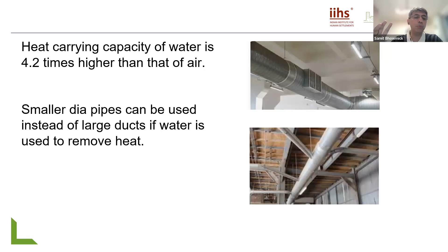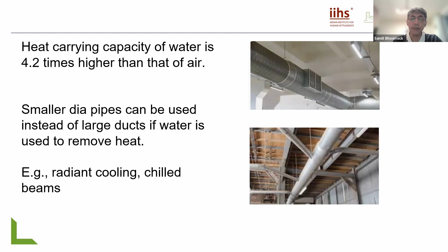It's been used in a lot of new buildings, at least in dry and convenient areas, with systems like radiant cooling or chilled beams, where the chilled water is brought as close as possible to the cooling load. This way you use smaller pipes to remove heat rather than large ducts, which would conventionally be used. Not only are we bringing it closer to the load, but since water is 4 times more efficient, we also consume less energy doing the same job.